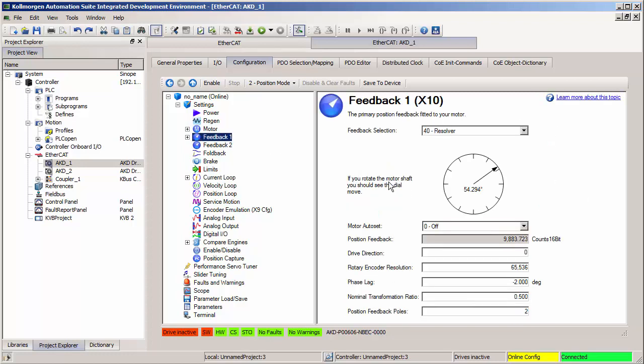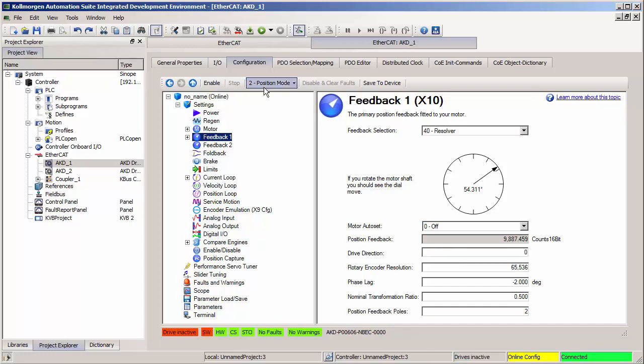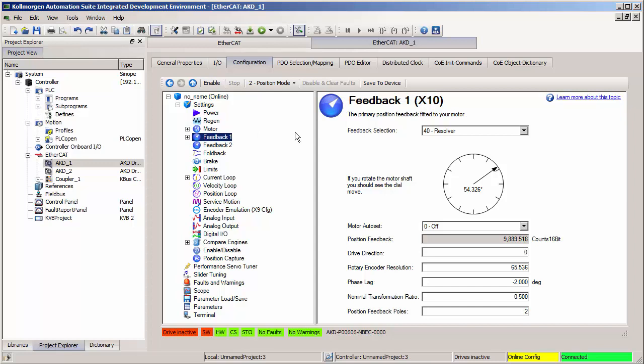You can also check the feedback tab to make sure that the right feedback selection is picked and that everything is communicating correctly. You'll note differences in the online configuration mode versus when a program is running: these options across the top are not grayed out. You now have the ability to enable or disable the motor from these screens, change the op mode from position mode to velocity or torque mode, and disable and clear faults if there were any active. You cannot do this while a program is running because the EtherCAT controller or master is in charge of all these parameters.